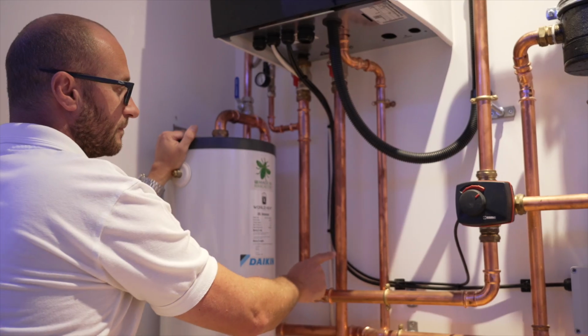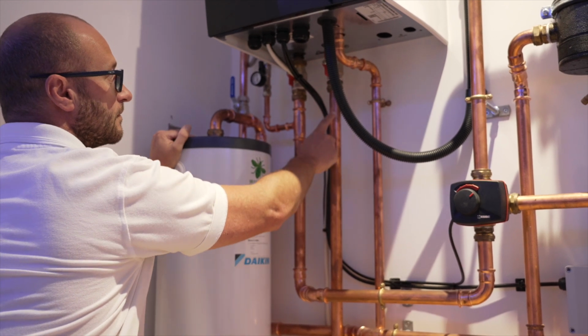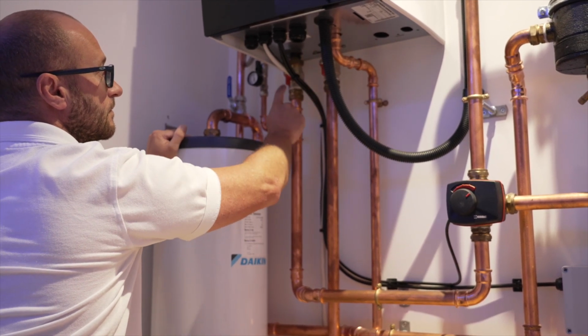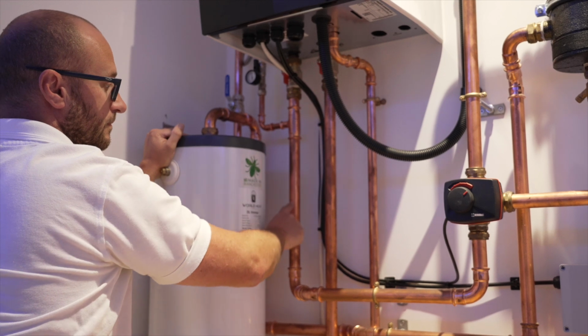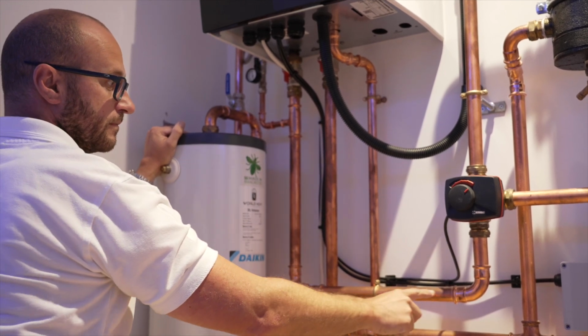When it comes to piping up the unit, think of this as an inline pumping station. Using the Hydrobox allows us to get much larger distances from the outdoor unit to the cylinder. So, from the flow of your outdoor unit, we connect this straight to the water in connection. The water then travels through the Hydrobox and is pumped out of the water out connection. From here, we can then go to our diverter valve and connect to the cylinder and space heating circuits. Wiring, commissioning, and basic fault finding of the Hydrobox we will look at later on.